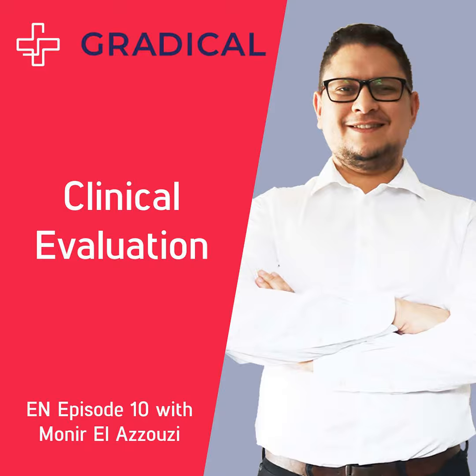Now, the principal mistake that manufacturers are making is with clinical evaluation. The principal reason for failing a certification is clinical evaluation. It's not the classification or the audit of ISO 13485. No, it's the clinical evaluation. We had a lot of manufacturers that failed to get certification and were about to stop their market in Europe and stay only in the US, and we were able to help them understand how clinical evaluation should be done. So do the clinical evaluation correctly and seriously, and 80% of your certification is nearly ready.